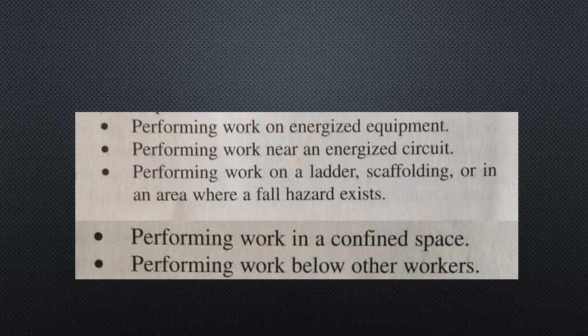Working on energized or live equipment is very dangerous. You must take additional safety precautions, which are discussed later in the chapter. Disconnecting the circuit being worked on does not guarantee your safety. After disconnecting the circuit, always test it using an appropriate testing instrument to make sure there is no current. The most dangerous situation is working on energized equipment you think is de-energized. Also identify any nearby circuits you may not have disconnected.